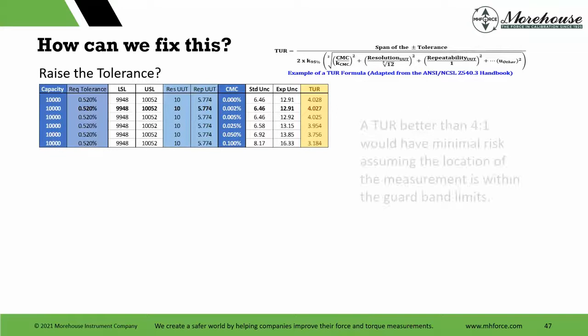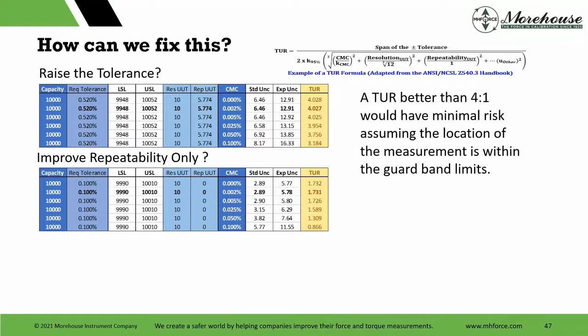Okay, so we say resolution still coarse, though I made that resolution coarse and I get a better, more repeatable measurement. So I take that to 0. Now I get a TUR. You can see the variable CMCs. Most people are down here, like at 0.025, 0.05. So I can get a TUR better than 1-to-1. It's still not 4-to-1 if that's the requirement.